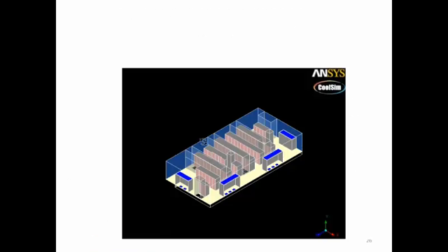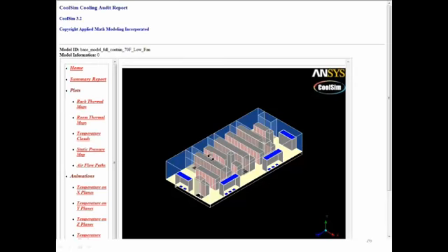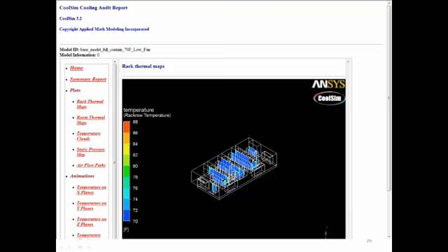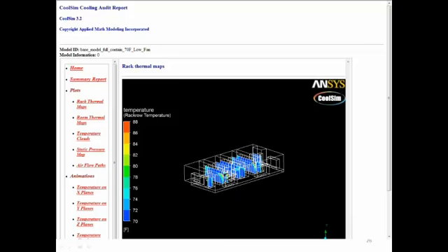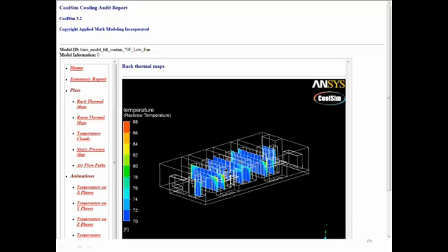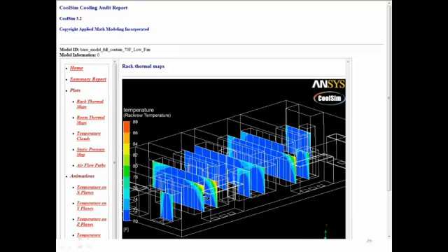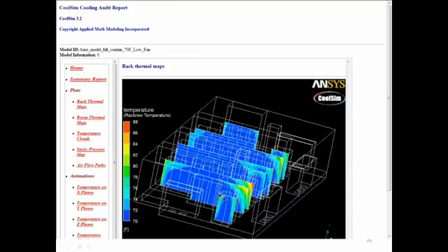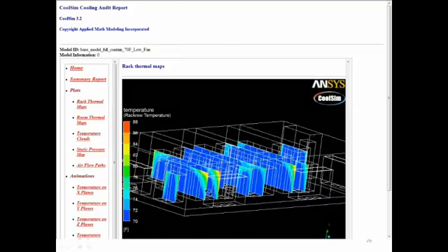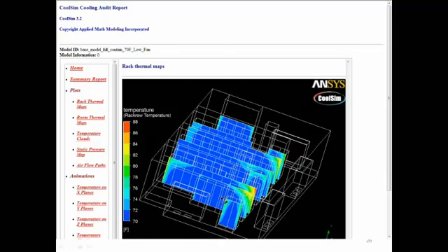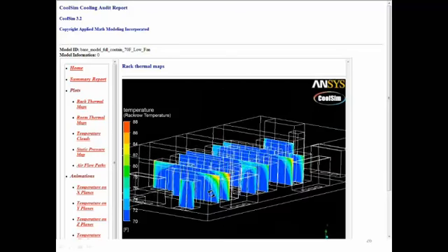So here's the final run. This is with everything in place. And let me just show you those rack inlets, Liz, so you can see where we're having issues. I know you know where it's going to be. You and I get to the point where we can tell where the leaks are going to be. They're always in the same place. It's corners. And again, that's just from air circulating. That's correct. Circulating back around. Yep. These are contained. It's probably a leak in my baffle, a little bit of a leak right there. Yeah, well, that would have to be through a leak in the baffle. Yep.